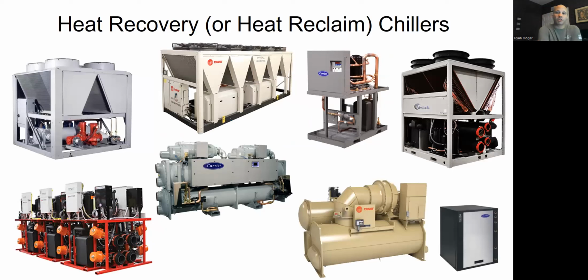There's also what we call a heat recovery chiller, or some manufacturers call it a heat reclaim chiller. Heat recovery and heat reclaim mean the same thing in this discussion. These are also heat pumps, but they are a little bit different in terms of how they are utilized. Sometimes it's the same machine, but usually it's not. The difference on these is that usually they do not have a reversing valve in them. They would do their reversing work with the water valving, or they would never reverse. They would always just be in one mode or the other. So I'll give you some piping examples to explain that here.